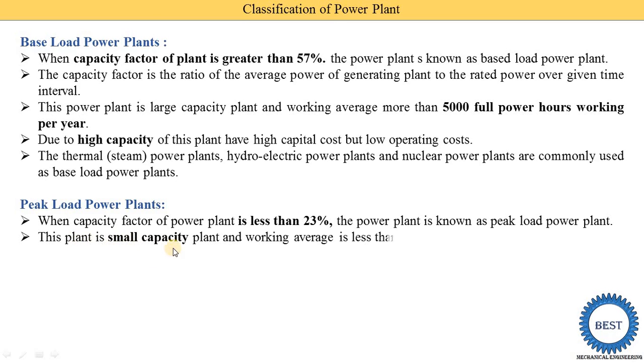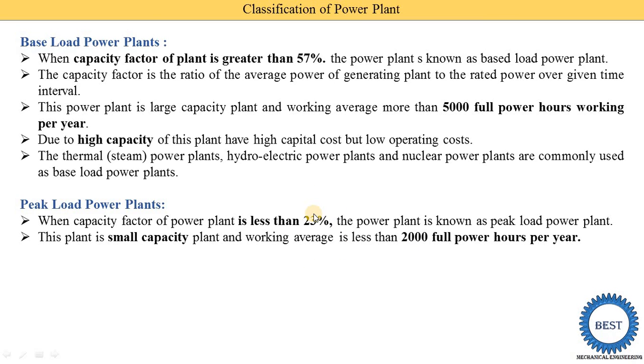The peak load power plant is a small capacity plant. Its working average is less than 2000 full power hours per year. In one year there are 8760 hours, and multiplying by 0.23 gives approximately 2000 hours. So a plant running less than 2000 hours per year is called a peak load power plant.